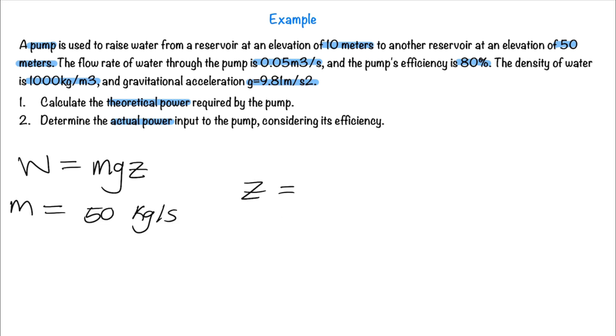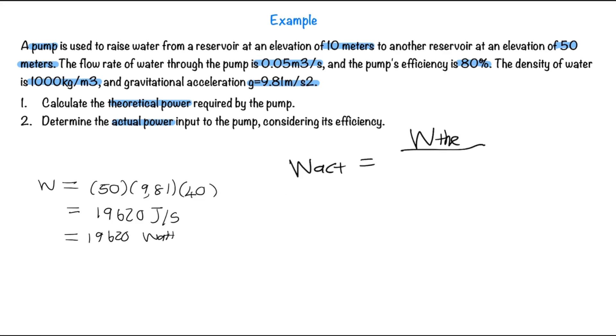Next we calculate the height difference, which is 50 minus 10, which is equal to 40 meters. We plug the values into our equation and get a work of 19,620 watts. Then to calculate the actual power needed, we just divide by the efficiency, which leads to the power being 24,525 watts.